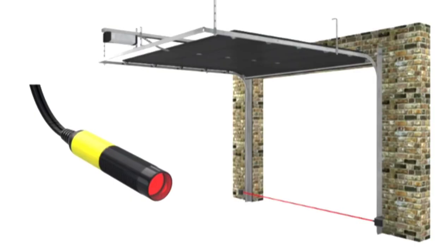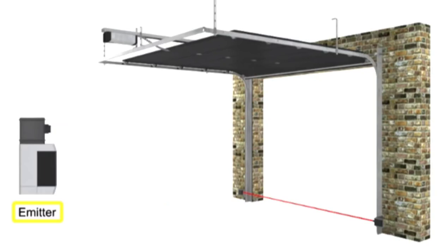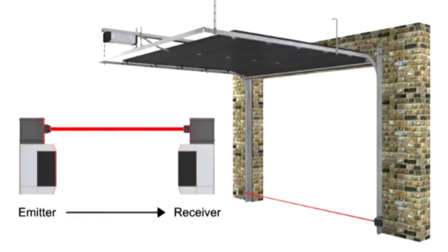Photoelectric sensors have the greatest detection range from 1 mm to 25 meters or more. They operate by the use of an emitter which transmits a beam of light to the receiver. When the light is normally being received, it is known as a light-operated mode. When the absence of light is required, it is known as dark-operated mode.